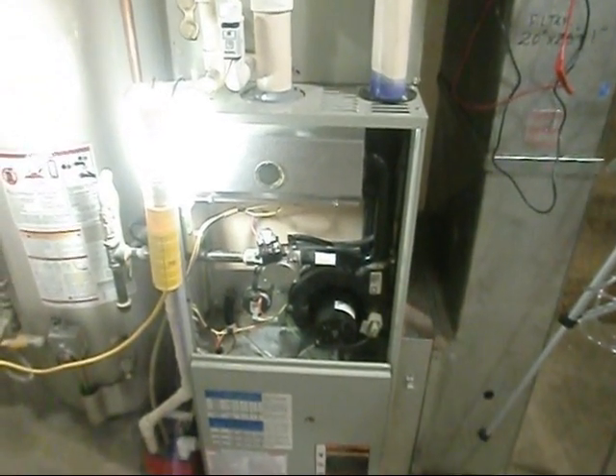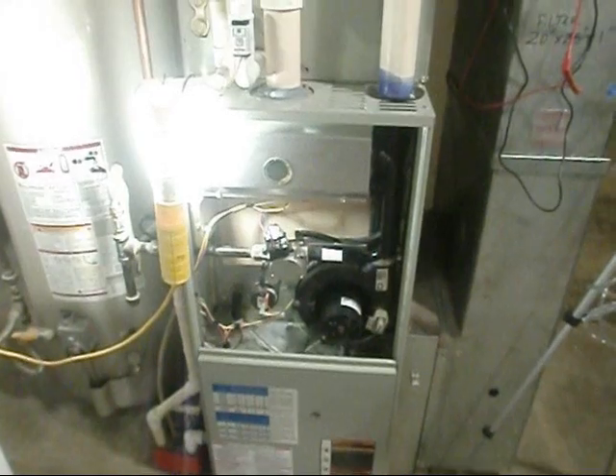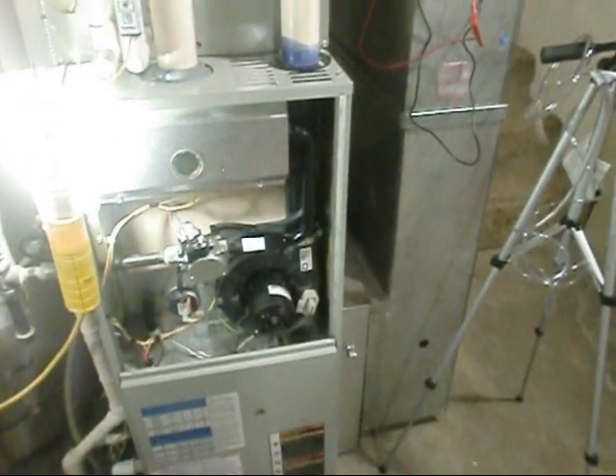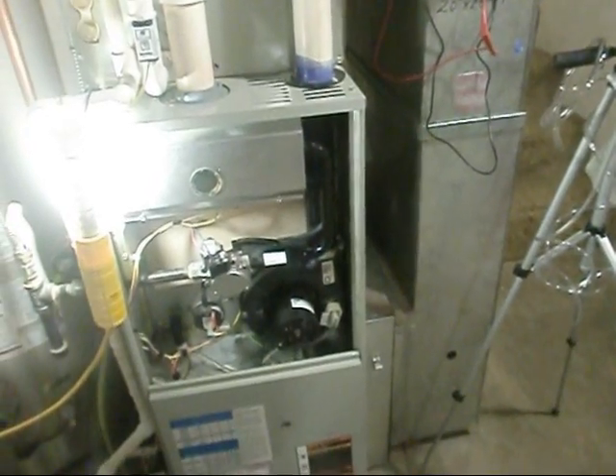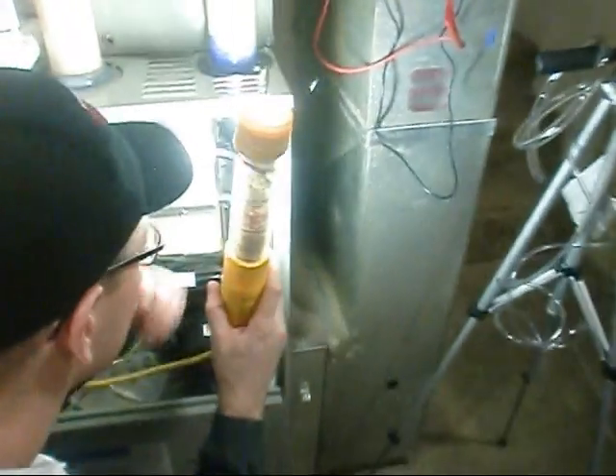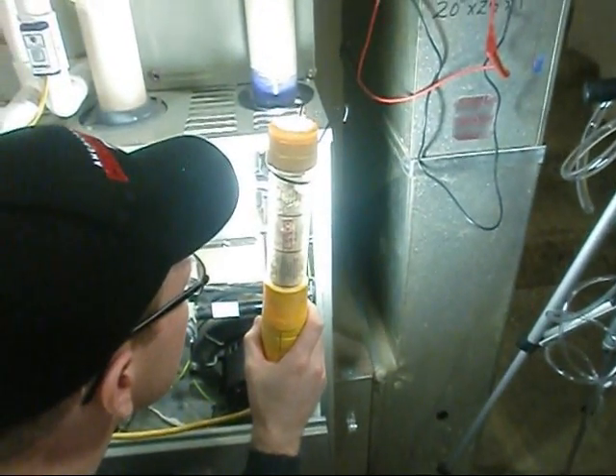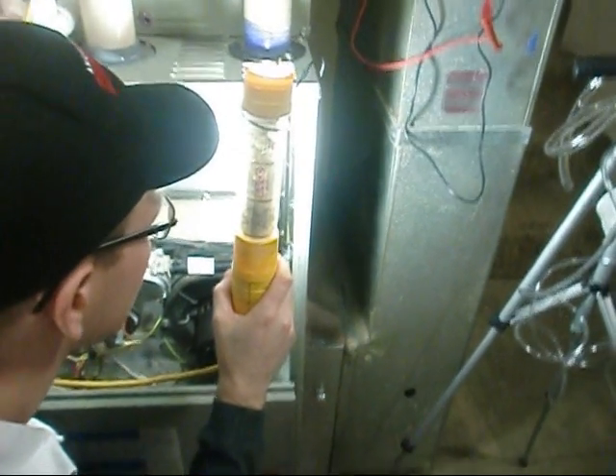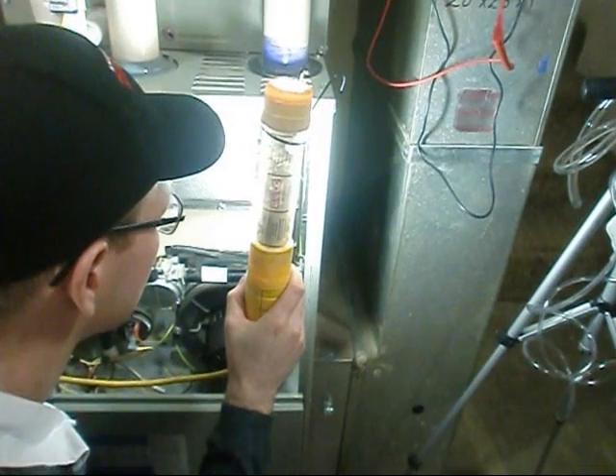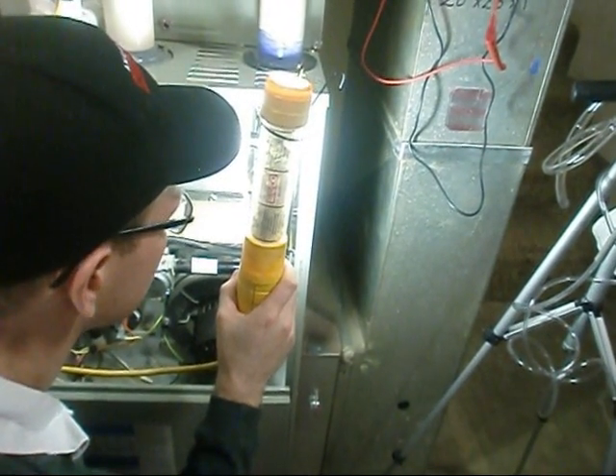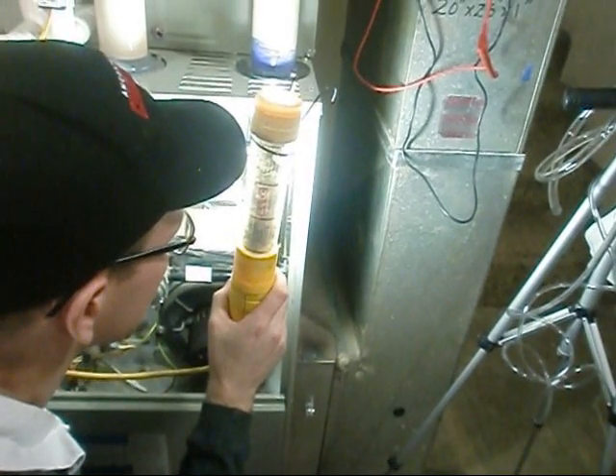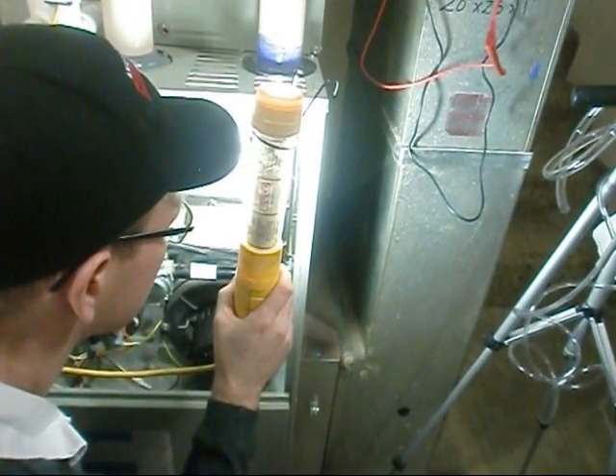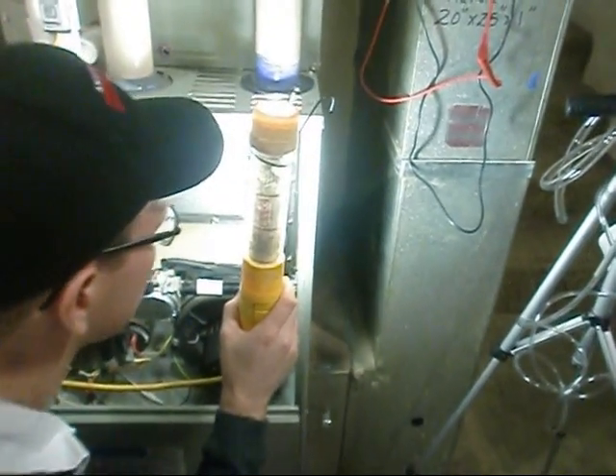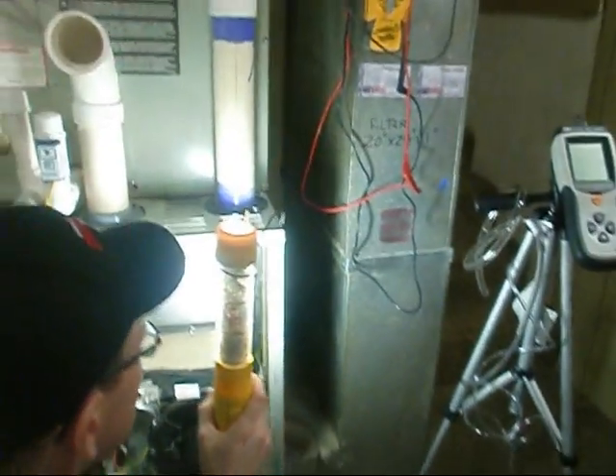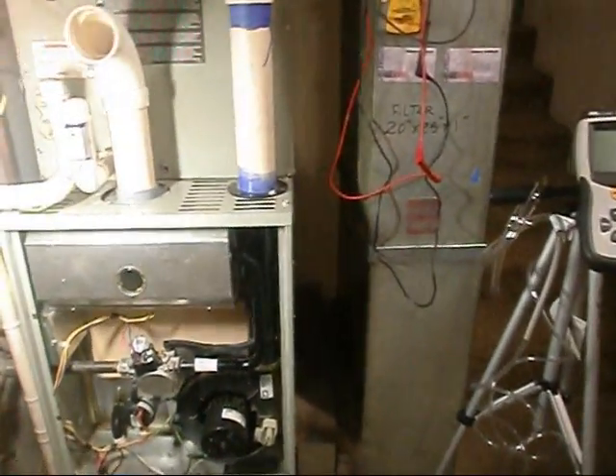There's not a whole lot to testing the gas valve. First, remember that chart you were looking at for static pressure? We're looking for the inlet side gas max and min. Maximum permissible gas pressure to the furnace is 13.8 inches water column for both natural gas and propane. The minimum gas supply pressure for input adjustment purposes is 5 inches water column. That's what we need to get started. Here in town it's probably going to be around 10.7 or so.